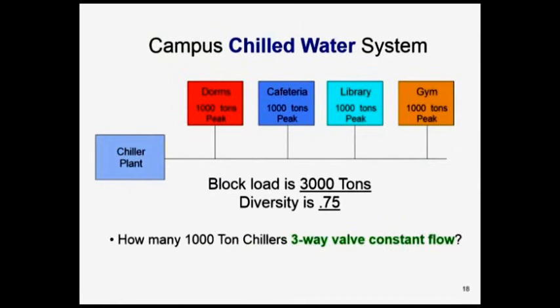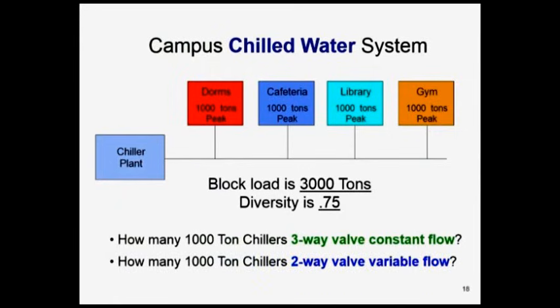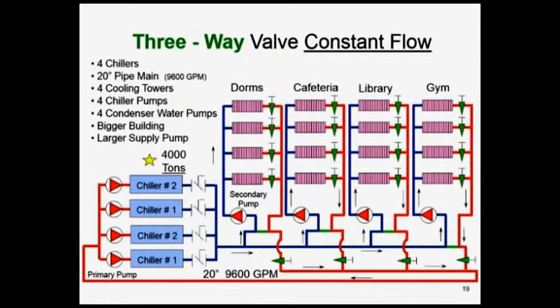If I had 3-way valves, the old constant flow, I'd have to have 4 chillers. I'd have to pump at a 10-degree delta T, 9,600 GPM, to pump the flow rate the same. I'd have the same flow rate all the time. If I went to 2-way valves, I can put in variable flow, only put the water where I need it and when I need it, and get away with three 1,000-ton chillers. And that's why 2-way valves have come into play energy-wise.